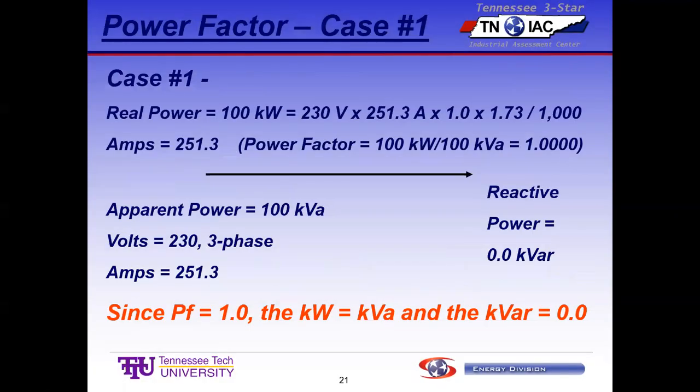So anyway, okay, here's the calculation. Case one, real power, 100 kW. And I don't know why I picked 230 volts for this. I mean, it's possible, it could be whatever. I guess if the voltage is lower, the current has to be bigger, and it makes a better example. But anyway, we'll use 230 volts in both cases.